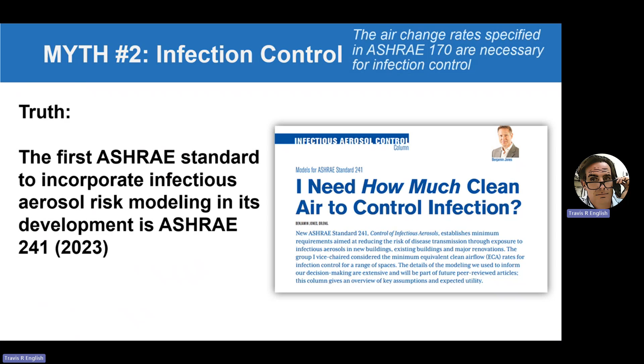You go get a copy of ASHRAE 170 and you search for the phrase infectious aerosols. It's not there. ASHRAE 170 does include ventilation requirements for isolation rooms, like 12 air changes per hour and negative pressure, but those measures are cited to the CDC's tuberculosis guidelines, 1994, updated in 2005. So the healthcare ventilation group itself has no experience developing standards for infectious aerosols. And I'm sure you can find somebody to disagree with me on this, but I don't think anybody in the healthcare ventilation group would ever claim that that group has any experience with developing standards for infectious aerosols. It's just not something that's ever been done.